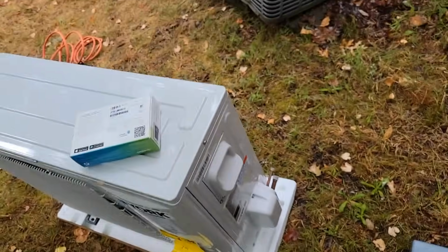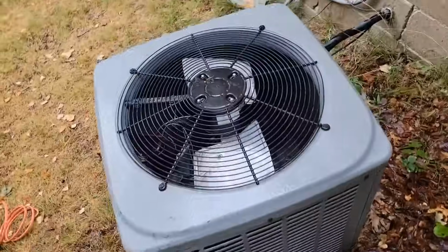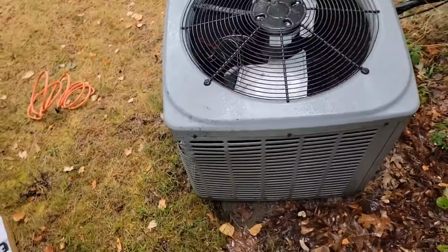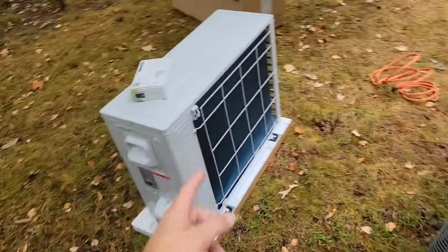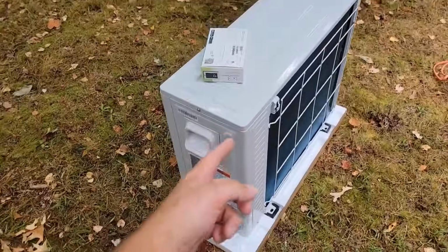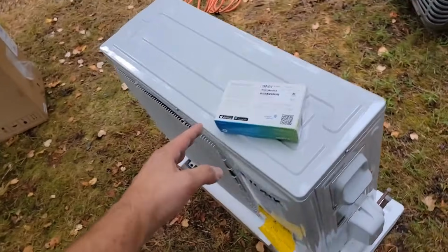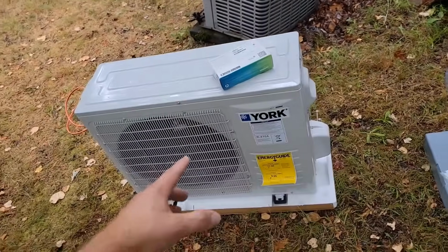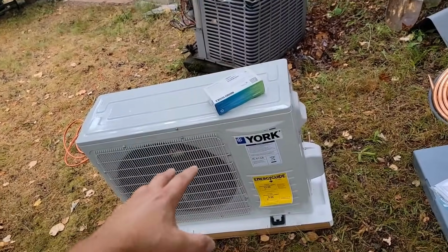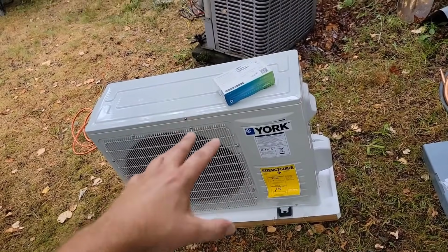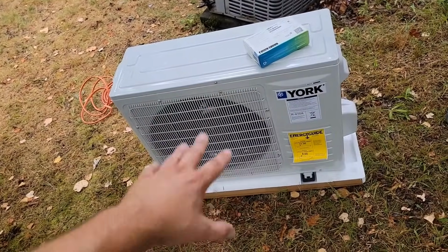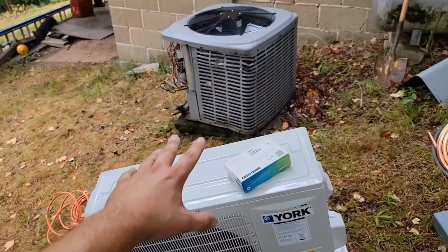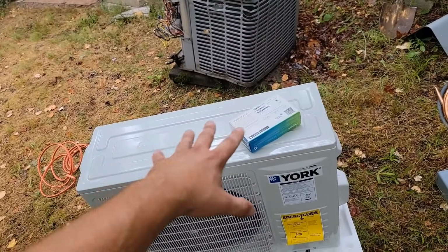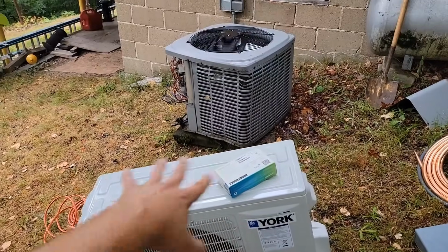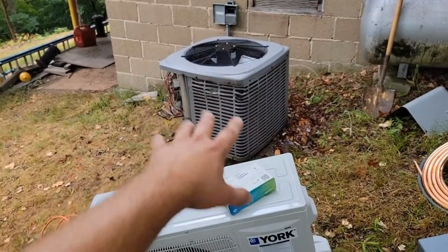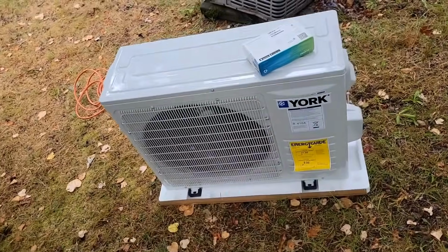Very nice. We're taking out this vertical discharge heat pump outdoor unit, and we're installing this horizontal discharge unit. It's really nice because this equipment is going to be a lot quieter, so it's going to have quieter operation. This side discharge is going to be nice because now you don't have to worry about the snow or debris that would fall on the unit and have to be cleared, otherwise the operation would be affected. We're not going to have that issue.